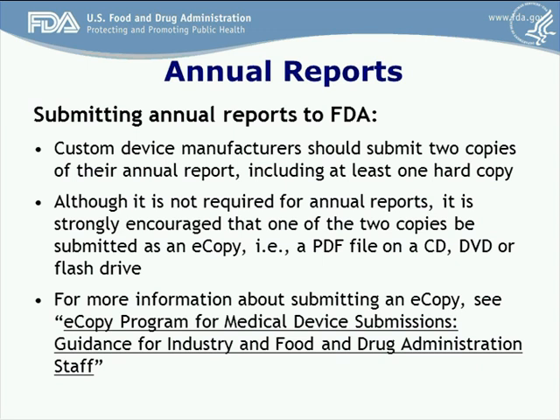When submitting annual reports to FDA, custom device manufacturers should submit two copies including at least one hard copy to the address contained in the guidance document. Please note that the room number for annual report submission has changed and is now room 2622, but the rest of the address is correct. Although not required, it is strongly encouraged that one of the two copies be submitted as an e-copy, for example a PDF file on a CD, DVD, or flash drive. For more information about submitting an e-copy, please refer to the guidance document titled 'E-Copy Program for Medical Device Submissions, Guidance for Industry and Food and Drug Administration Staff,' the link for which is provided in the custom device exemption guidance document.